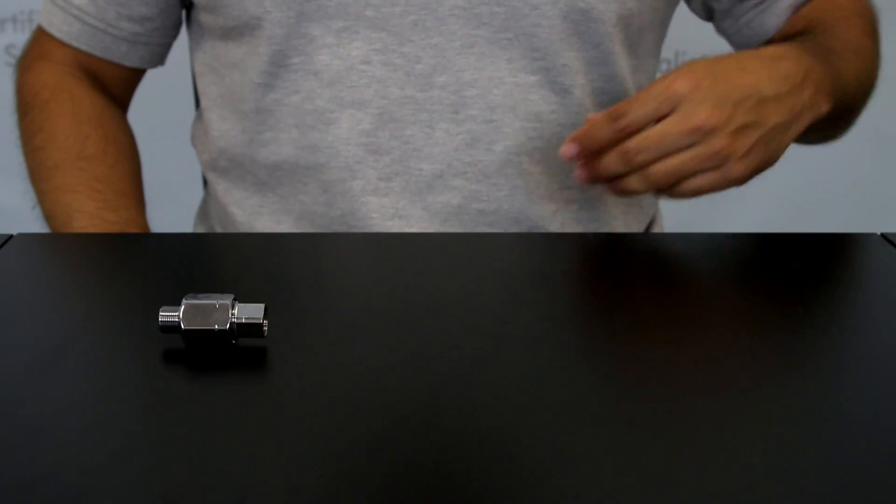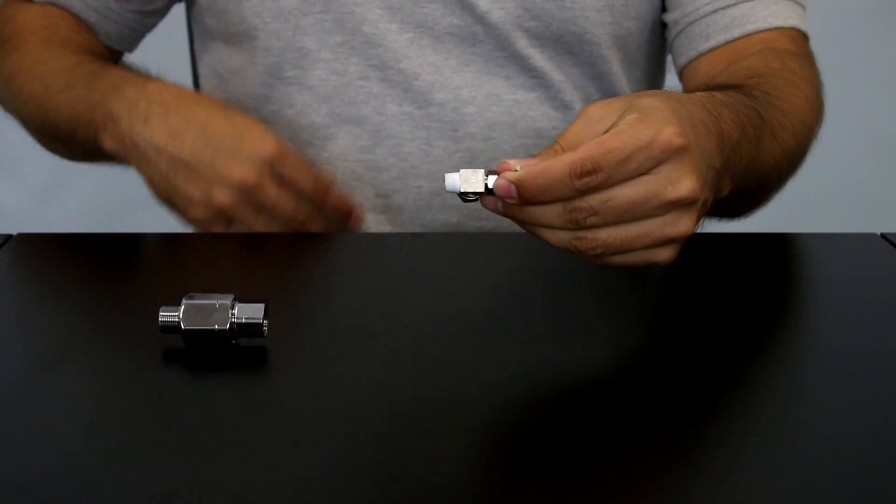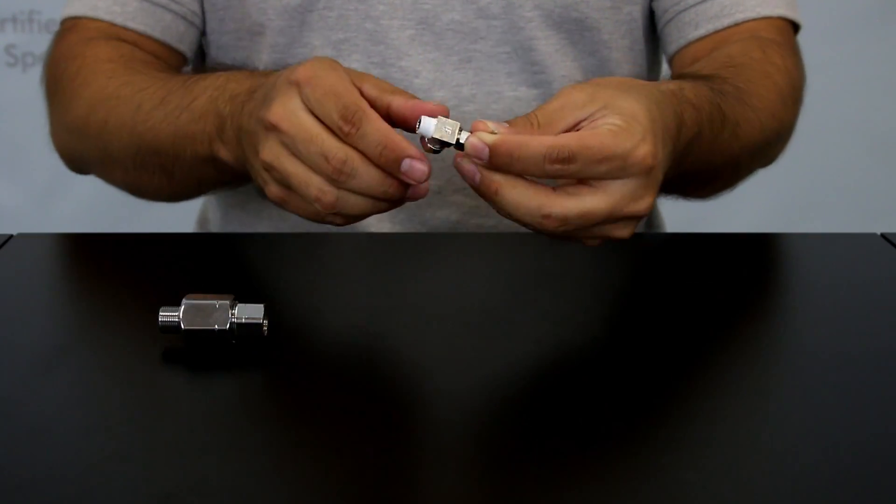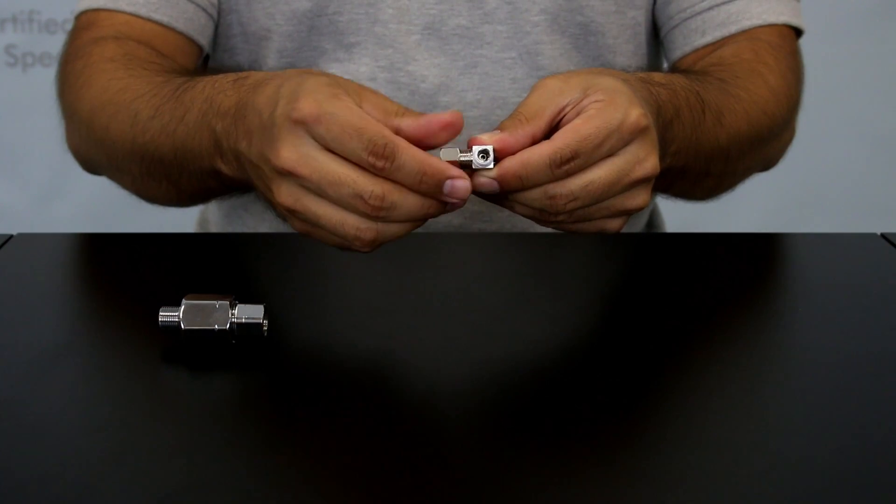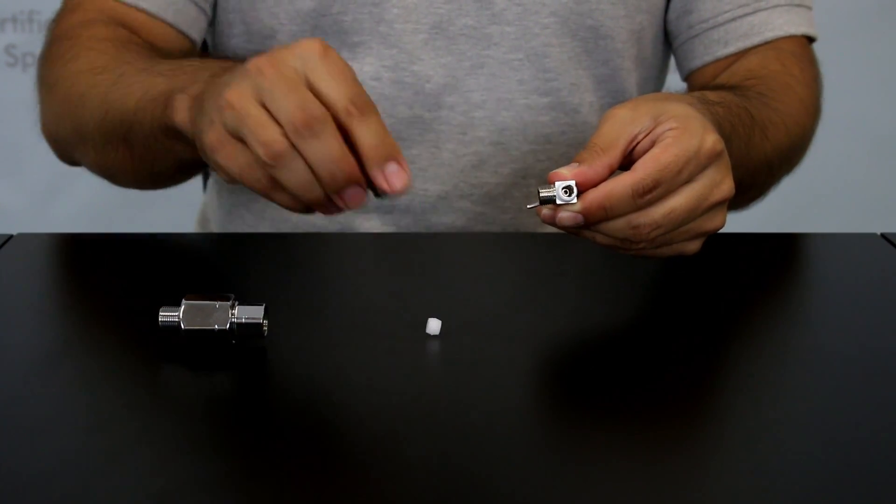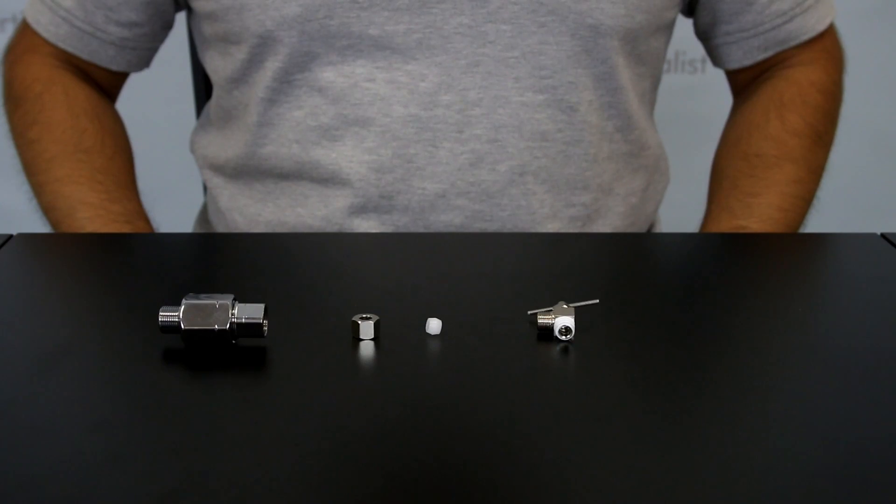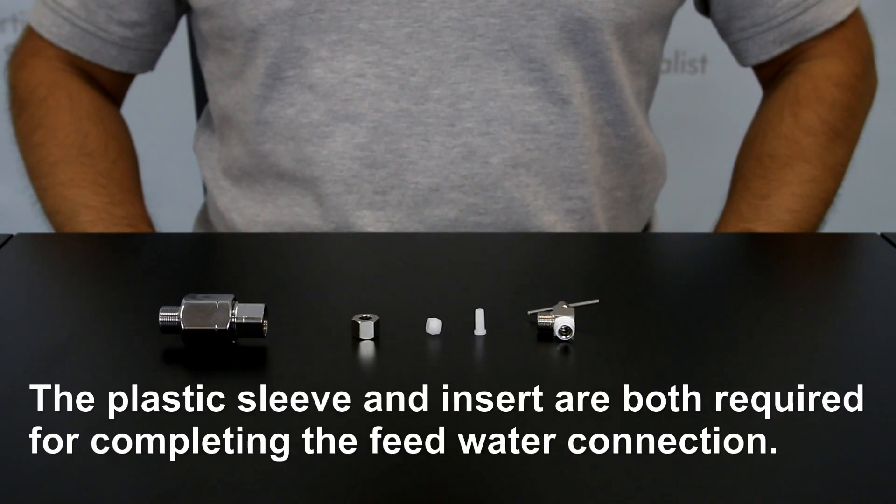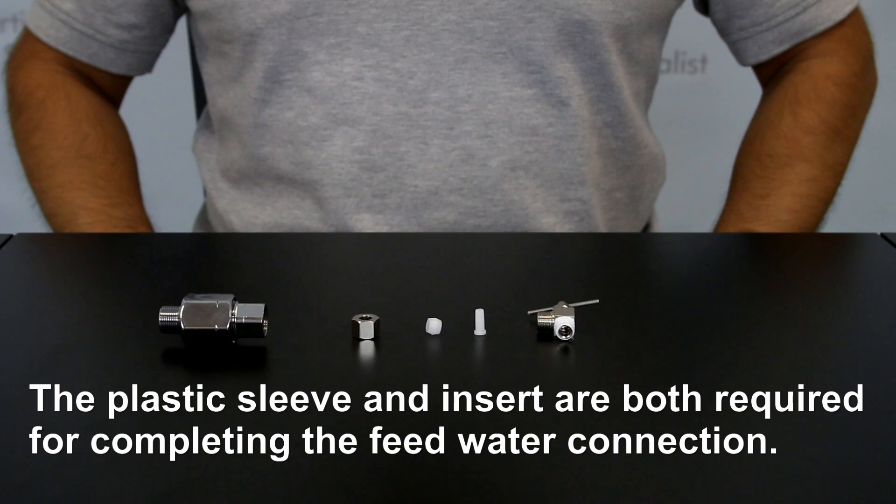To assemble the needle valve portion that screws onto the feed water adapter, apply five to six wraps of Teflon tape to the needle valve threading. Upon unscrewing the metal compression nut you will see a plastic sleeve is placed inside. You will also notice a plastic insert is provided. Please note the sleeve and insert are both required for the feed water connection towards the end of the installation.